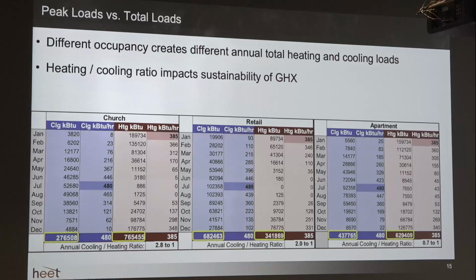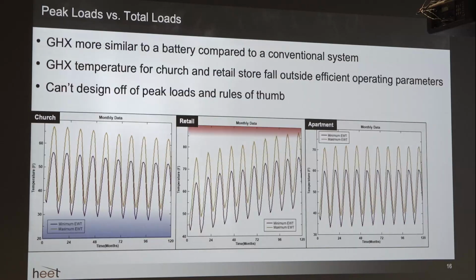And how this affects the ground loop and why it's important is because, and this is especially true for a vertical ground heat exchanger scenario with a lot of conduction, right? You have a fixed volume of earth that you're exchanging heat with. And so it's more similar to a battery in that case compared to a conventional system. There are nuances, right? And each project is unique.